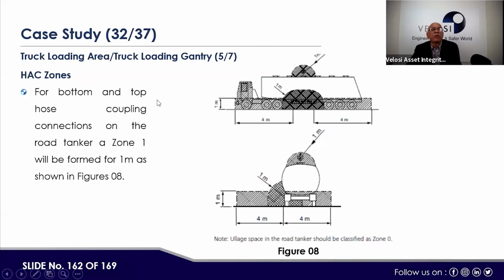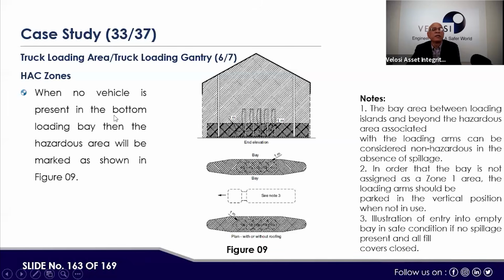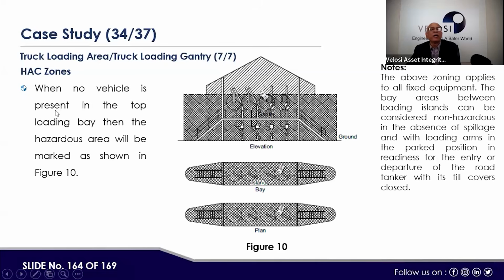Then for the bottom and top hose coupling connection on the road tanker, a zone 1 will be formed for 1 meter, shown in this figure. Then when no vehicle is present in the bottom loading bay, the hazardous area will be marked as shown in the figure, on the bottom side. Then when no vehicle is present in the top loading bay, the hazardous area will be marked this way.